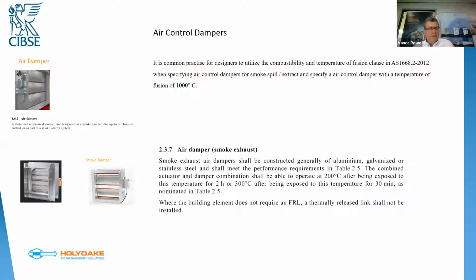Air control dampers, these do cause a bit of an issue in the industry. It's common practice for designers to use the combustibility and temperature of fusion clause in AS 1668.2 when specifying air control dampers. And generally, quite often, particularly in the Melbourne region, we see them specified with a fusion temperature of 1000 degrees C. In that case, we tend to find that steel dampers are used. The interesting thing about steel dampers is that they do tend to leak more than aluminium dampers. It's much harder with the structure of the damper itself to get an effective seal in a steel damper, particularly at low temperature. You'll find that steel gets quite pliable quite quickly.